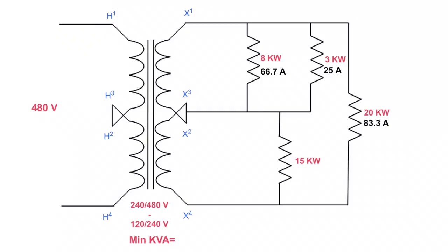Now this is the tricky one. We've got a 20-kilowatt load, but it is across line one and line two, so this is a 240-volt load. So I'm going to take 20 kilowatts divided by 240 volts — do not get caught in the trap of using 120 again — and you're going to get 83.3 amps. Last, we've got 15 kilowatts connected to the 120-volt load because it's connected to the neutral. 15 kilowatts divided by 120 gives you 125 amps.